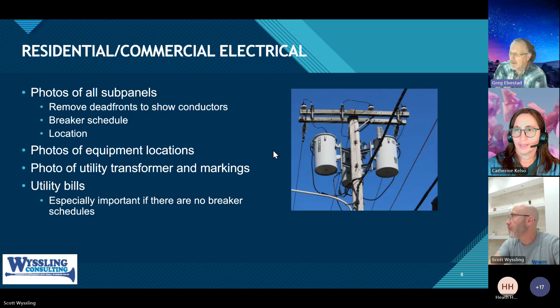There we go. If you'll notice on the transformer on the right-hand side of the photograph, if you zoom your screen, you can see there's a 50 stenciled on the can. That's done for the power company personnel's purposes, but also it's helpful for people like Catherine and me to decide how big the transformer service is. That 50 means 50 kVA, a 50,000 watt transformer. So this transformer bank on the pole is a 150 kVA transformer set with a three-phase service going to a structure.